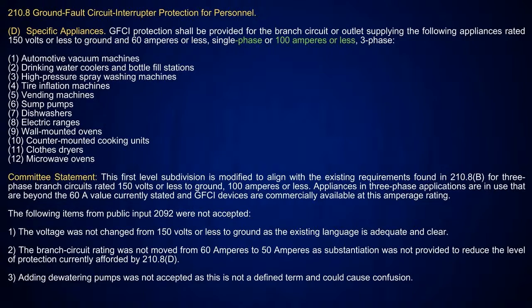The thing that gets me is, if you read what 210.8D says, it says GFCI protection shall be provided for the branch circuit or outlet supplying the following appliances. It doesn't say an outlet is going to supply. That means it's already there, you're plugging into it. Here, they're not saying there's an outlet when you hardwire it. They're telling you to provide protection for what? The branch circuit. If everything already has an outlet, then why don't you just say it that way?